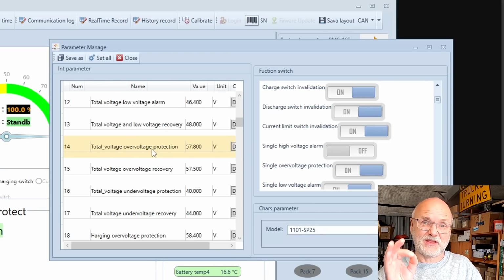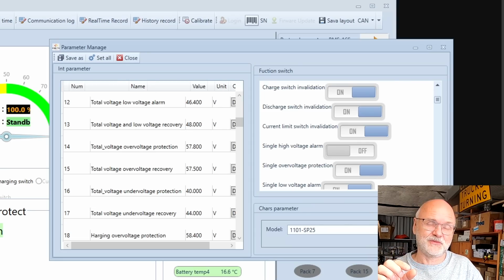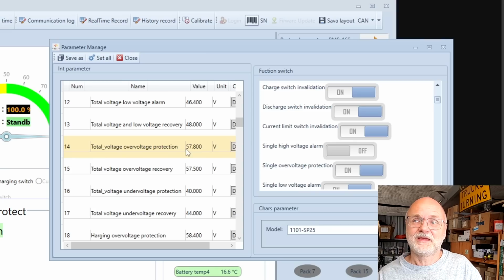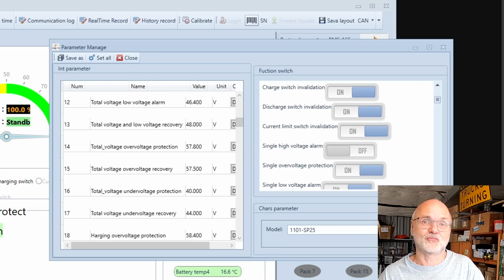But for pure safety purposes, I have still set the total voltage over voltage protection to 57.8. If something goes wrong with my Raspberry Pi and it doesn't limit my charge current to 57 volts anymore, I still have the 57.8 volts, and when we hit that we will get an over voltage protection and the charge current goes to 0 - it tells all the chargers to stop charging altogether, something is not right.